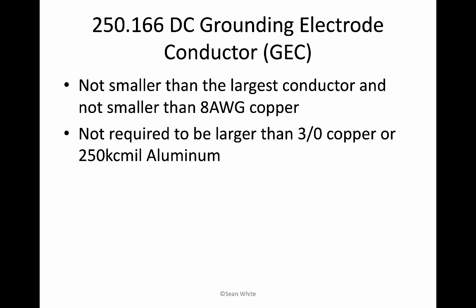So what would be these exceptions? You're doing some little small off-grid ground mount thing like a water pump. That would possibly require a DC grounding electrode conductor, or just some system that's only DC that doesn't have any alternating current. So not one of these big things that most of us are trying to do, where we're connecting big buildings to the grid and energy storage systems and big off-grid systems. Most of the systems that would require a DC grounding electrode conductor would be under a kilowatt, not something that we would be dealing with too much.